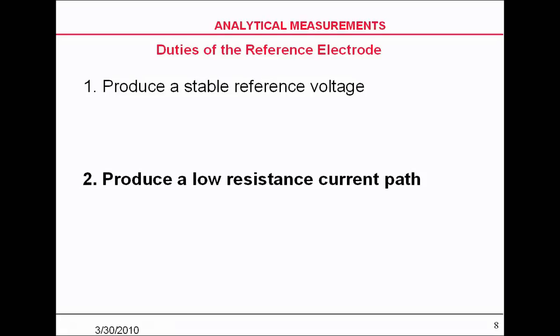To measure pH, you basically use two components: the reference electrode and the measuring electrode. Even in what they call combination electrodes today, that combination electrode will be broken down into two or three sections. It'll have a reference electrode, a measuring electrode, and a temperature compensator.